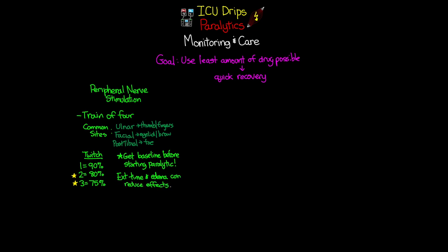If you notice decreasing or diminishing twitching but haven't made any changes to the medication — especially for patients who had been achieving a good twitch at a stable rate — you may need to increase the output on the stimulator over time. This gives us an objective, quantifiable way to assess how much paralytic our patients need.